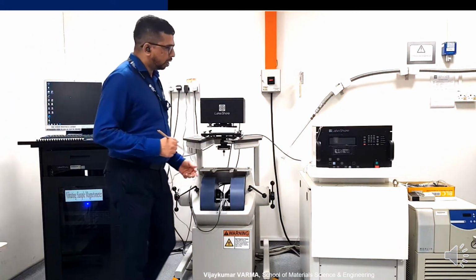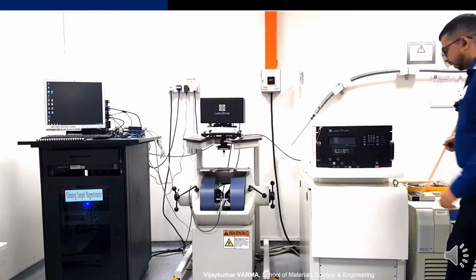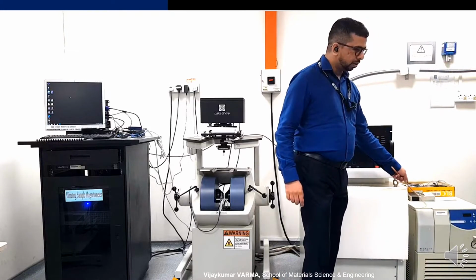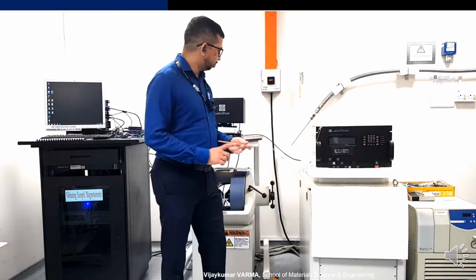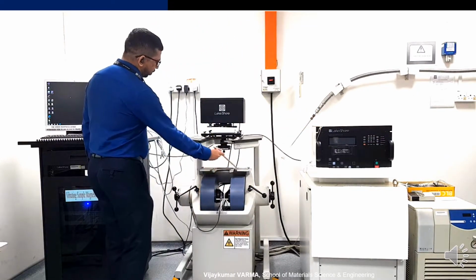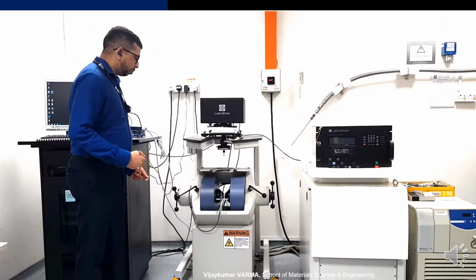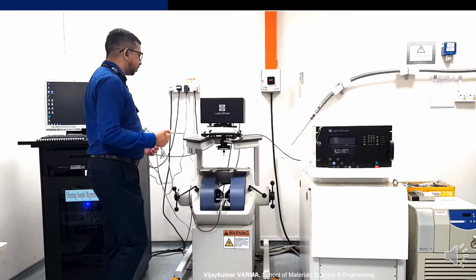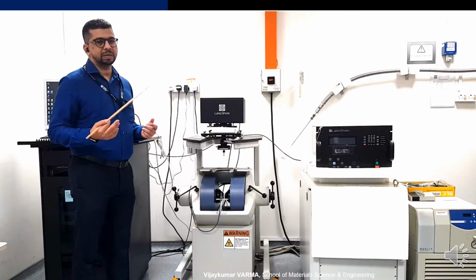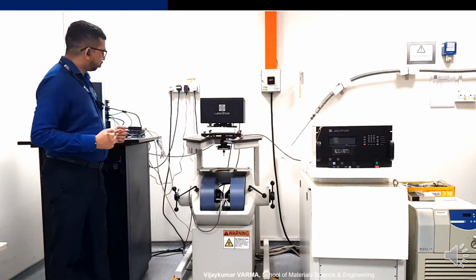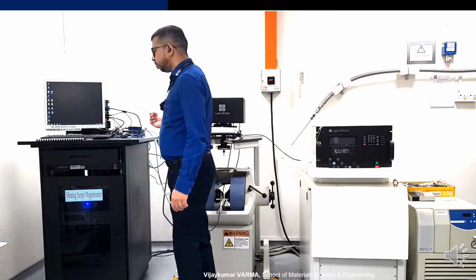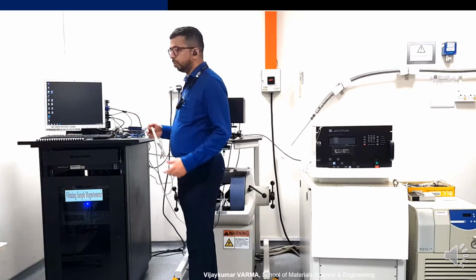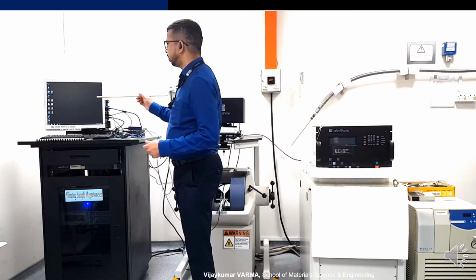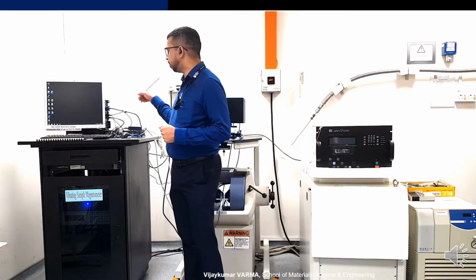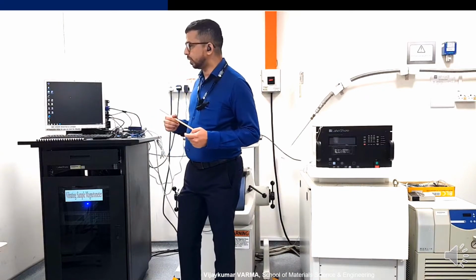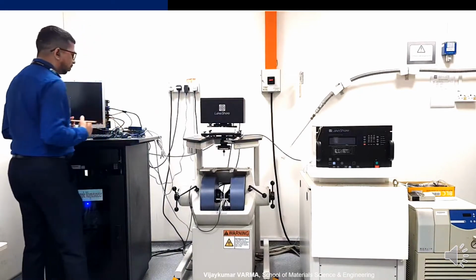So what are the main components of the system? Let's start with this side. Here we have a chiller, we have a power supply, then we have the main component of the system, which is this magnetic coil in the form of an electromagnet, and then the head of the system, the core of the system where the main action happens, which is this head drive unit. And then of course we need to have software-based measurement. This system communicates with the software, and then the software calibrates the measurement. So here we have the computational unit, or you can say control unit. These are the main components of the system.